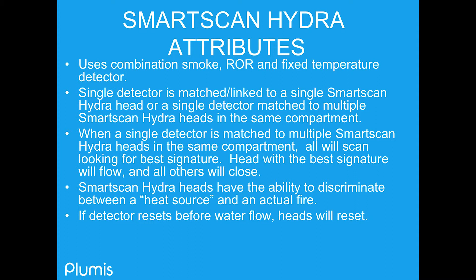Sprinklers are great, and mist systems are even greater, fantastic stuff. My only concern is we often trade some passive fire protection measure for an active one, and if a component of that active measure fails, we're left with a debacle. So if cellar occupancy becomes legal in New York and they just put in mist systems, is there backup power, is the wiring fire rated, and so on? It looks like dynamite stuff, but that trading of passive for active protection would be my only worry.